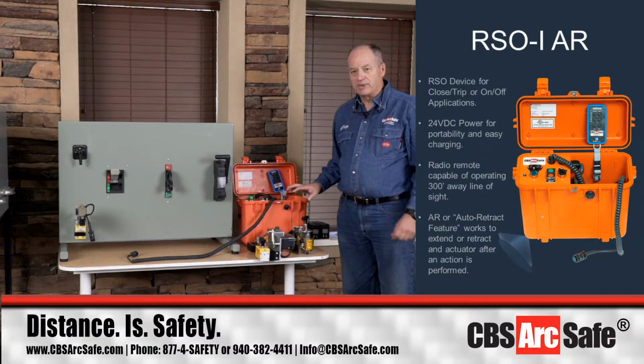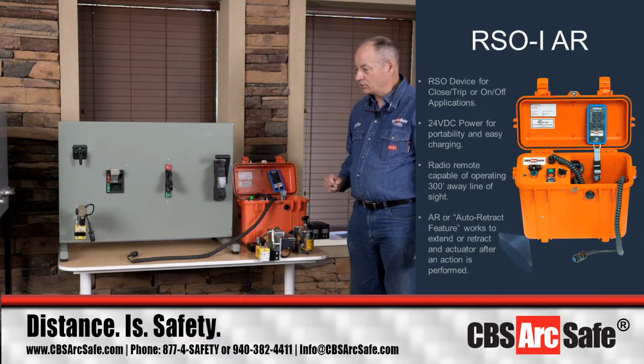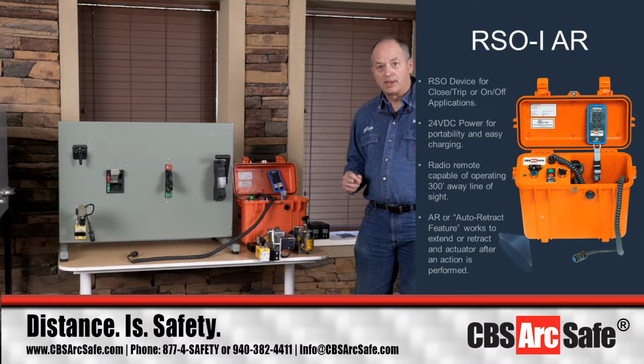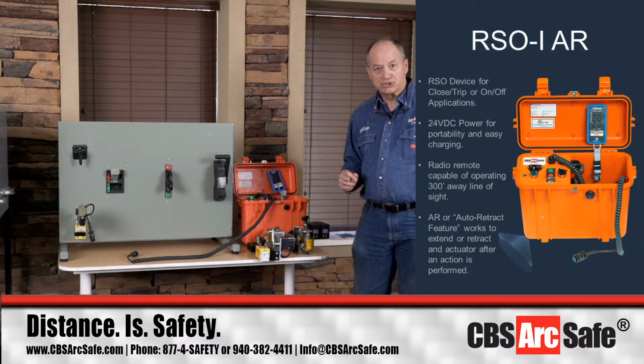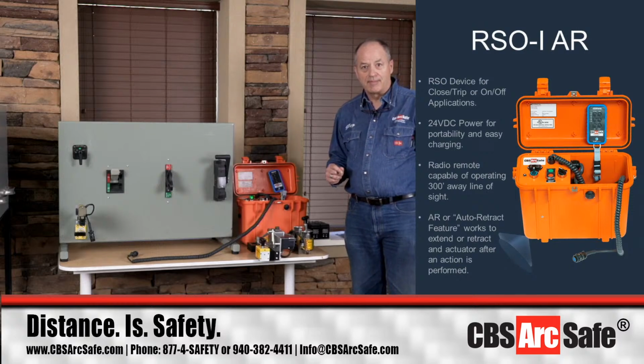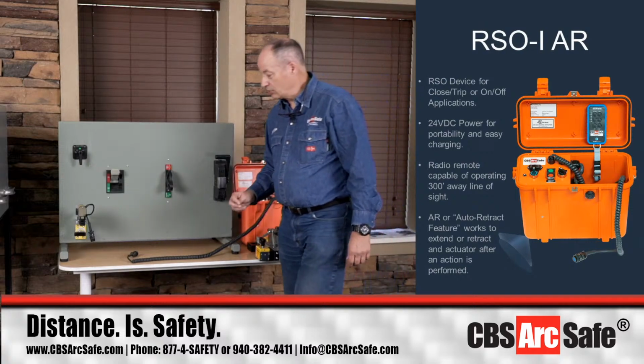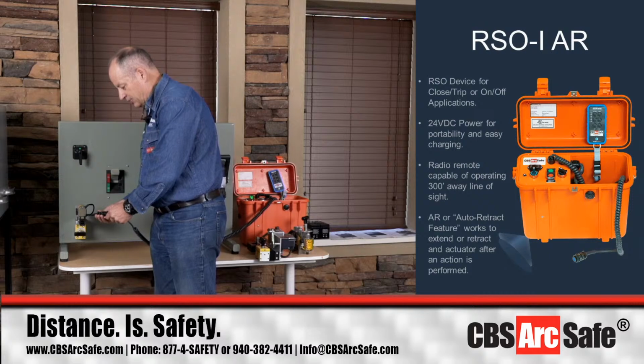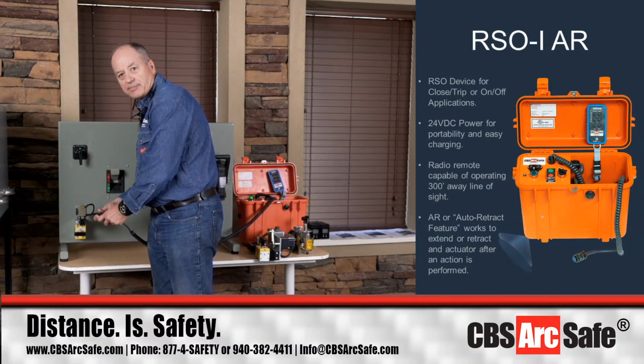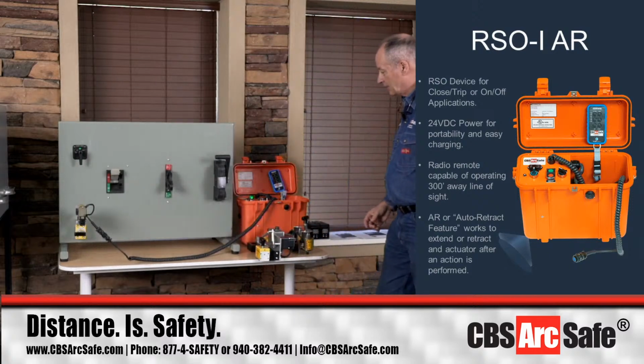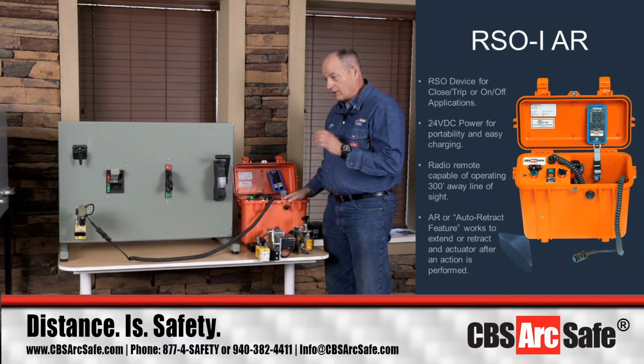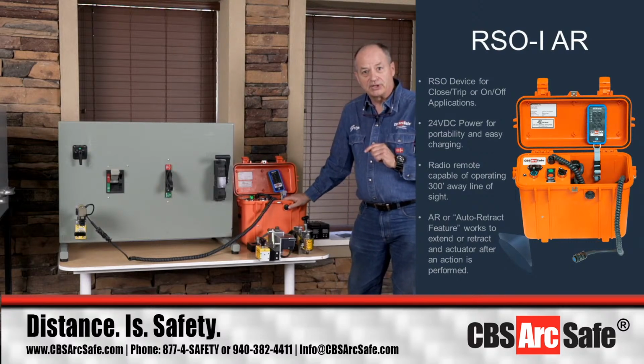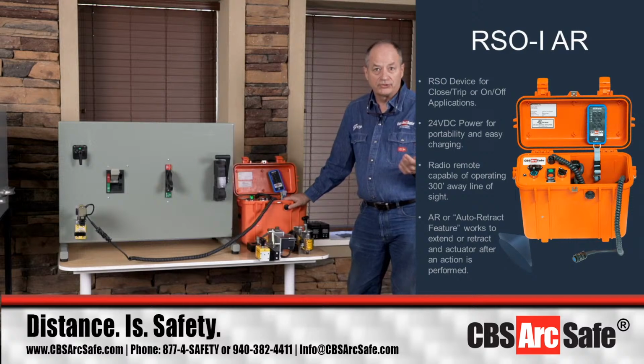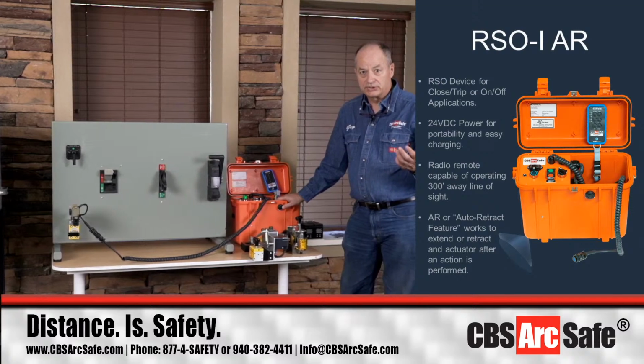The first actuator we made with AR functionality was actually the RSA-II HD, a heavy duty push button actuator. The first breaker we had a customer ask for it was the General Electric Magnablast breakers, because they said, I don't want to have to use my bang stick and stand right in front of this beast to push that push button on the breaker when it doesn't want to open. So we've got the RSA-II HD to answer that call from the electrical industry. It's wound up being used on other medium voltage breakers like a GE Power Vac or a Powell Vac, or other things that require a stout push to be able to open.